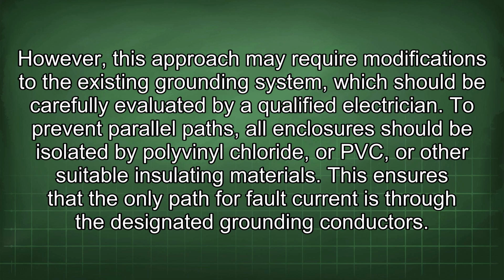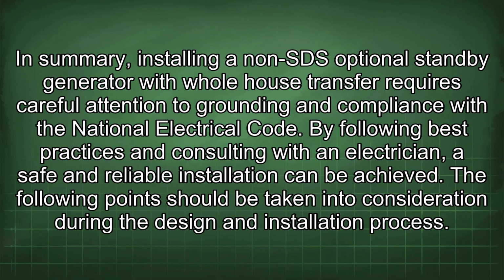To prevent parallel paths, all enclosures should be isolated by polyvinyl chloride, or PVC, or other suitable insulating materials. This ensures that the only path for fault current is through the designated grounding conductors. In summary, installing a non-SDS optional standby generator with whole house transfer requires careful attention to grounding and compliance with the National Electrical Code. By following best practices and consulting with an electrician, a safe and reliable installation can be achieved. The following points should be taken into consideration during the design and installation process.